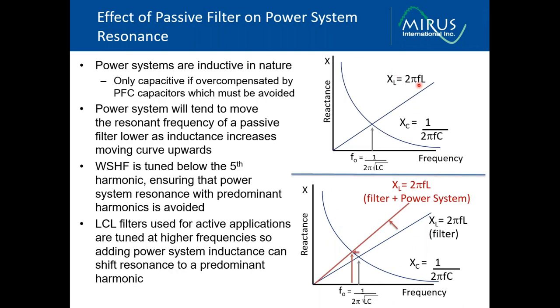So if we look at the power system and we understand that the power system is inductive, the only time a power system is capacitive is if it's overcompensated by power factor correction capacitors. So the power system is inductive. That will cause the inductive curve to move upwards. As the inductive curve moves upward, the resonance frequency shifts to the left, or goes to a lower frequency, a lower harmonic number. Wide spectrum harmonic filters are tuned below the fifth harmonic. So if you have a shift due to the power system, it's going to shift you even further below the fifth harmonic and away from the predominant harmonics introduced by six pulse rectifiers: fifth, seventh, 11th, 13th, and so on.